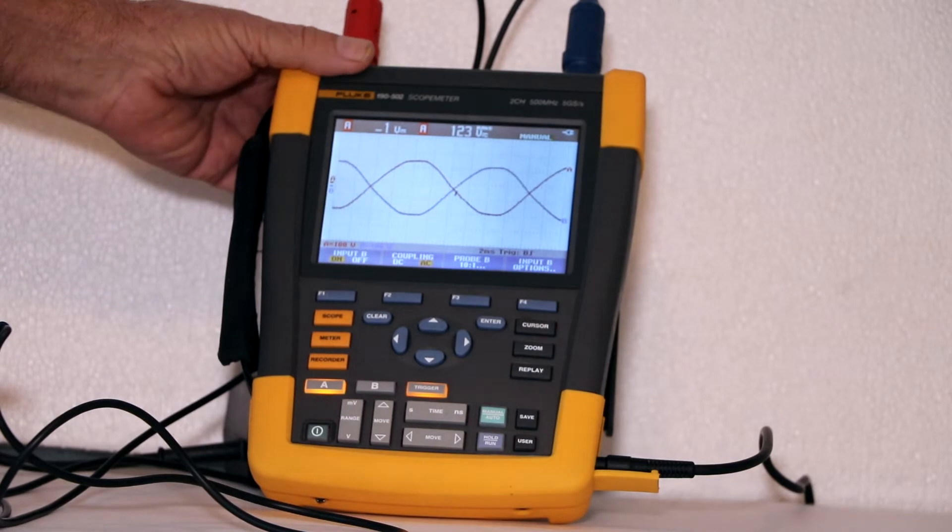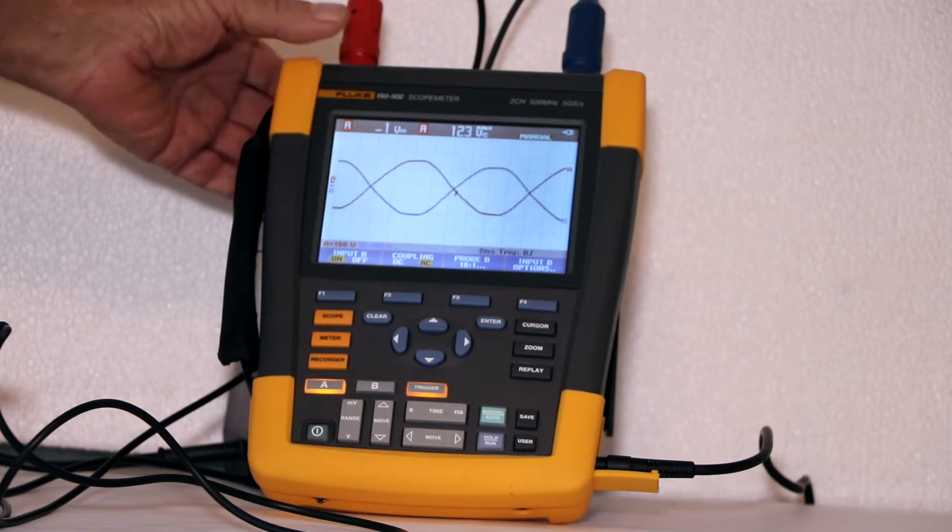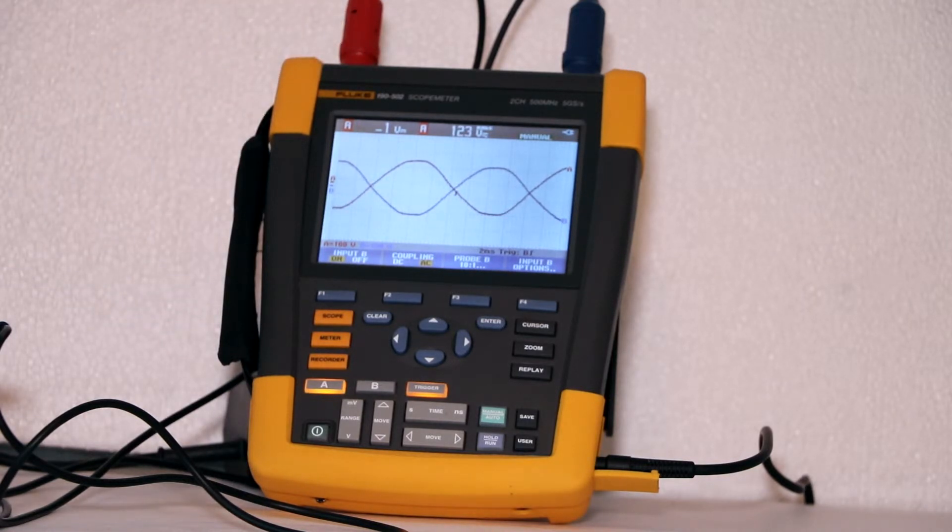Using a handheld battery operated oscilloscope that is totally isolated from the premises electrical system ground and that has channels that are isolated from one another such a hookup is permissible without fear of fault current.